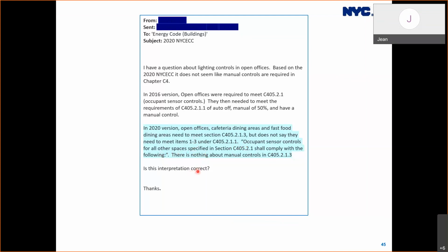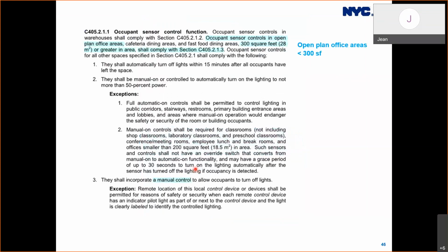So we'll go straight to this section and see what it says. If you pull up C405.2.1.1, this section actually points to another section for open plan office areas of 300 square feet or greater. So this means open plan office areas of less than 300 square feet must comply with these sections. And one of the requirements is that they shall incorporate a manual control. So for open plan office areas less than 300 square feet, a manual control is required.